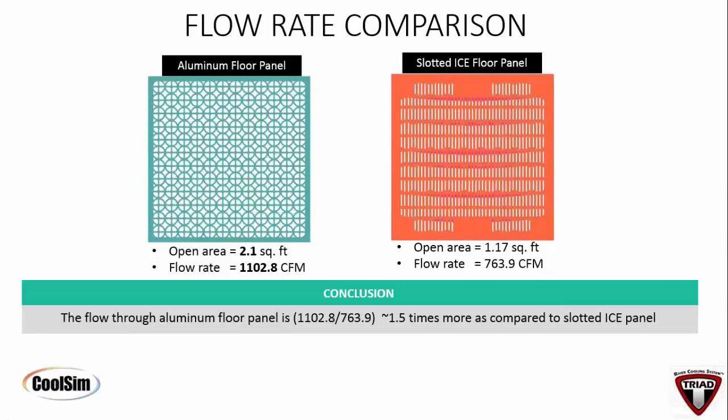All right. We've got one last comment for you. Your CFD setup shows the primary airflow going from row to row, not along an aisle. However, most data centers are laid out with flow along aisles, not across them. Yeah, I think this is the same question, Gary. I get this a lot. Can we see analysis of the flow moving along the aisle instead of perpendicular to the aisle? And the answer is yes. We just have to change the orientation and squirt the air in the other direction. It's easy enough for us to do. It may be something you want us to do in the future.